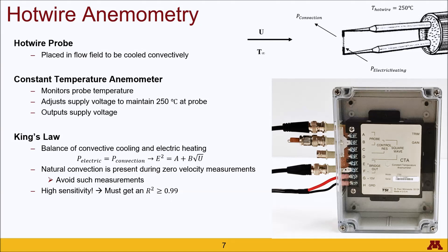Keep in mind during the calibration process and any measurements that the hot wire probe is incredibly fragile and also very expensive. Try to avoid any contact with the wire itself and be wary of it burning out, because it does do that from time to time. In that case you can contact the TA and they will replace the probe with a new one.